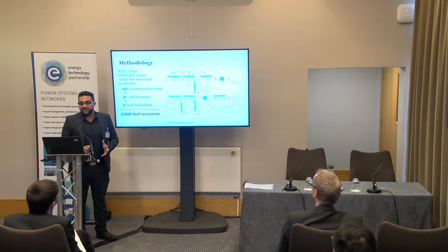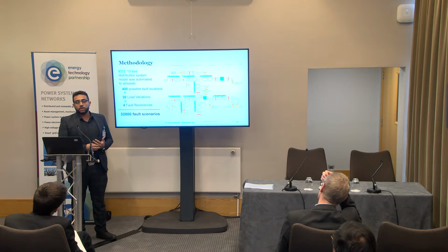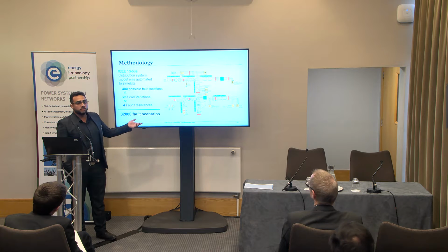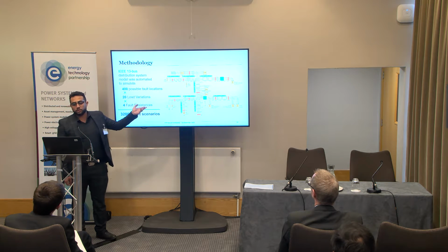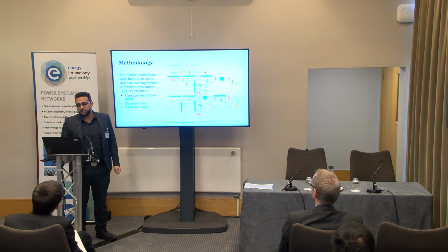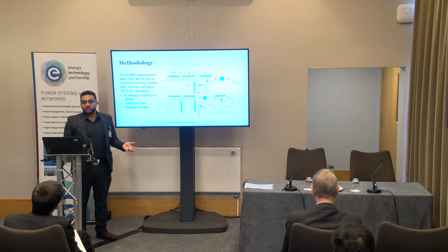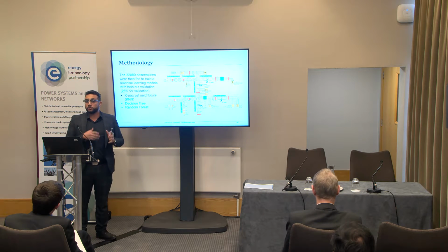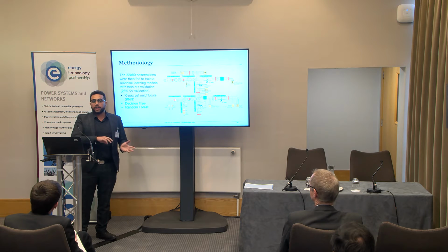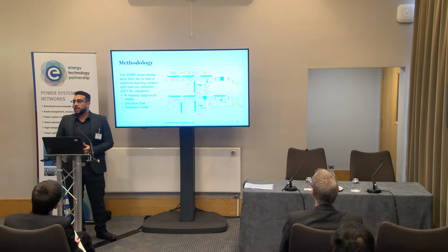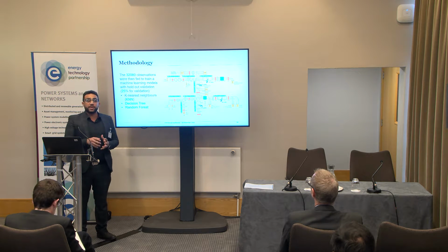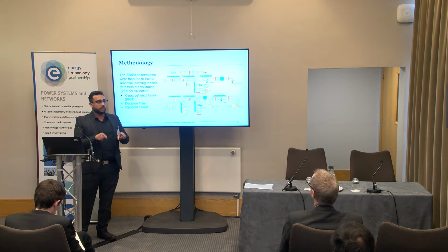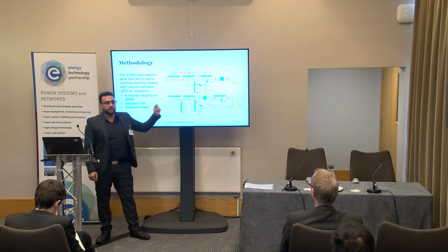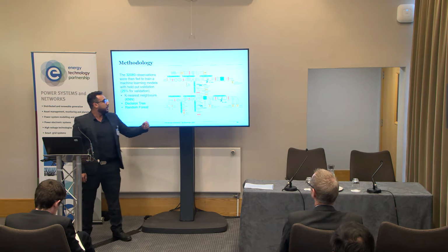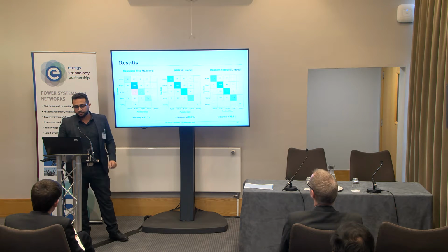So now I have to validate this idea using a distribution system, the IEEE 13 bus, and I simulated 32,000 fault scenarios using different variations from fault location, load variation, and fault resistances. Using this big data set of fault location and smart meter readings, I can feed it into different machine learning models and see if they can use just the smart meter readings around the system, these yellow boxes, to locate where the fault is.